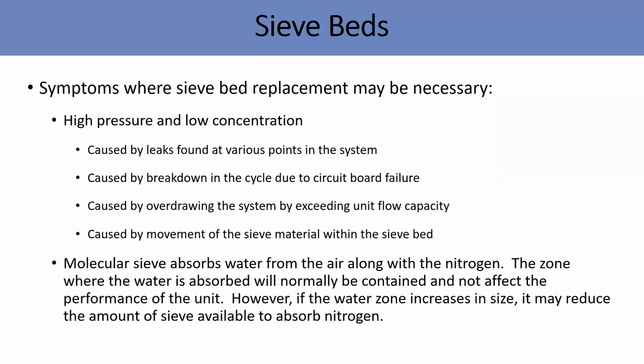So symptoms of sieve bed failure are basically caused by high pressure and low pressure concentration, leakage on the system, breakdown of cycle due to circuit board failure, overdrawing the system beyond the existing unit flow capacity, and movement of sieve bed material within the sieve bed itself. So remember, when you talk about the sieve bed, water will always go through that system, basically humidity. So if you are near a very humid place, the lifespan of your sieve bed is much shorter actually.